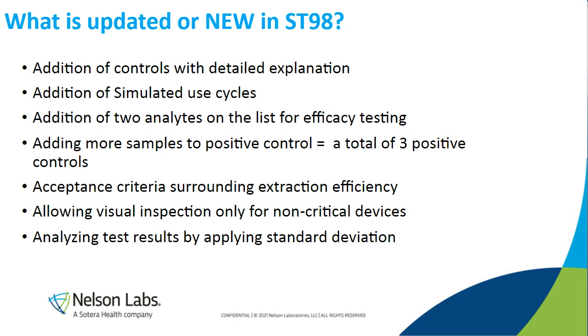Addition of controls with detailed explanation. The standard has adopted some controls in this final draft. Addition of simulated use cycles, which was in the FDA guidance document for validation and labeling for reusable medical devices. However, nothing out there had any information on it, but this standard that will come out will have it. Addition of 2 analytes for testing, also increasing the controls. And acceptance criteria regarding results. How are the results going to be presented now as they have been historically?